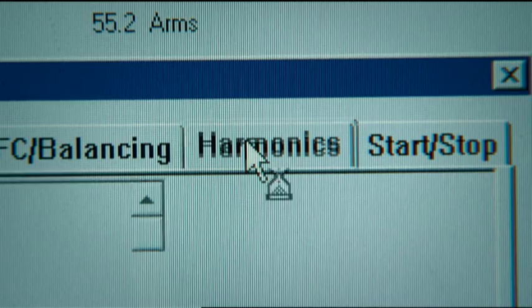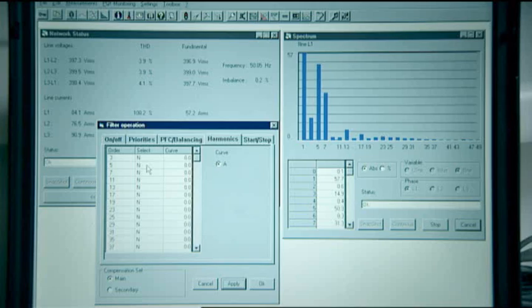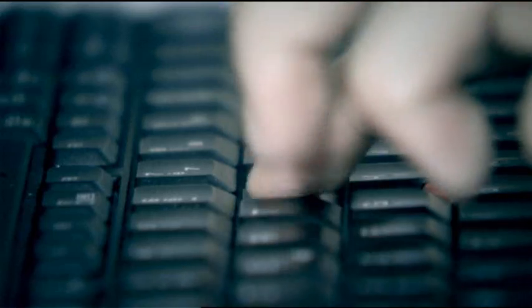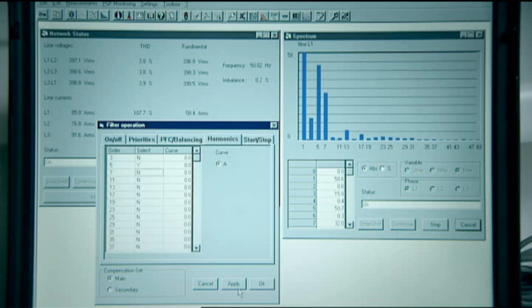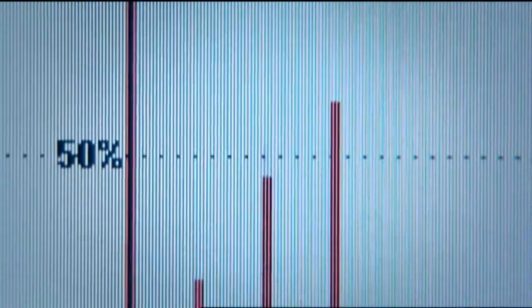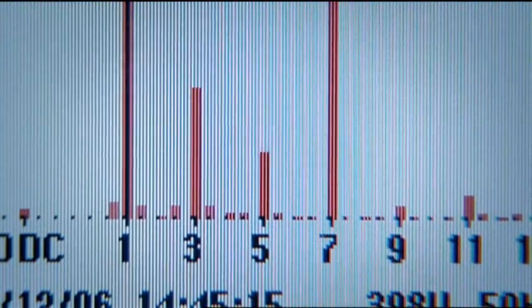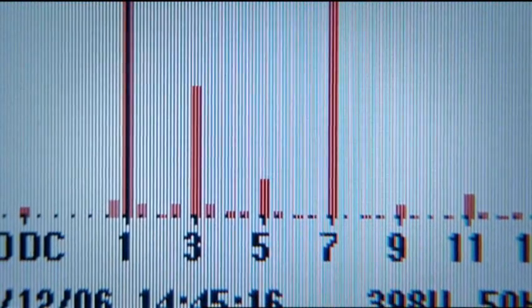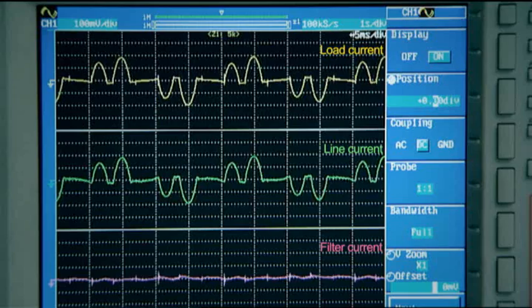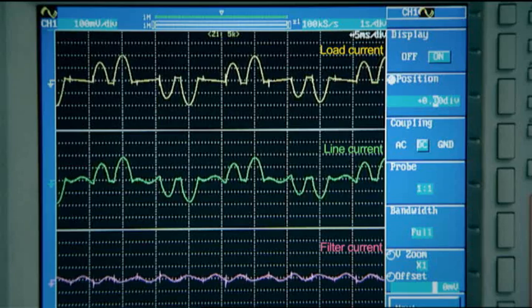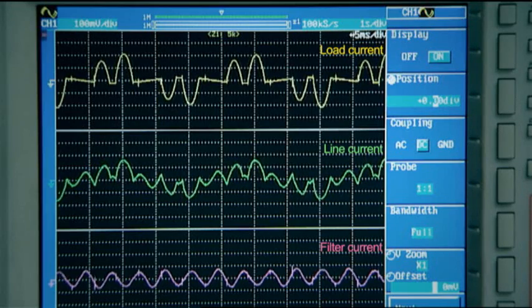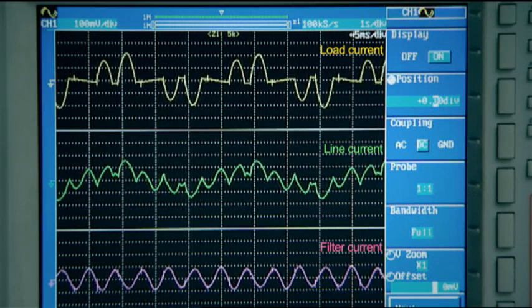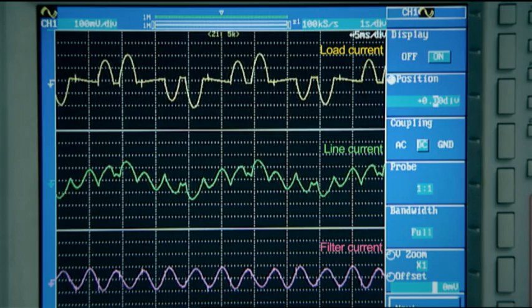The 5th harmonic is now selected. The active filter will only filter that harmonic component. As the filtering target is set to zero, the filter will take out the entire 5th harmonic generated by the load. The spectral analysis clearly indicates that the 5th harmonic has disappeared from the line current waveform.